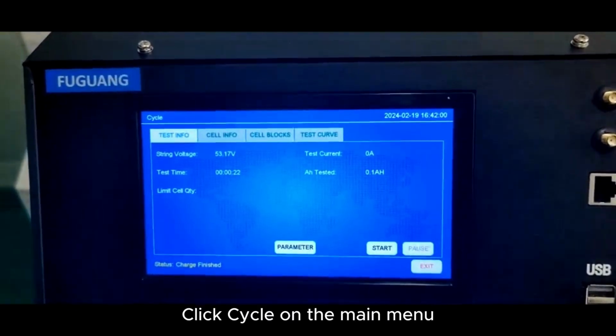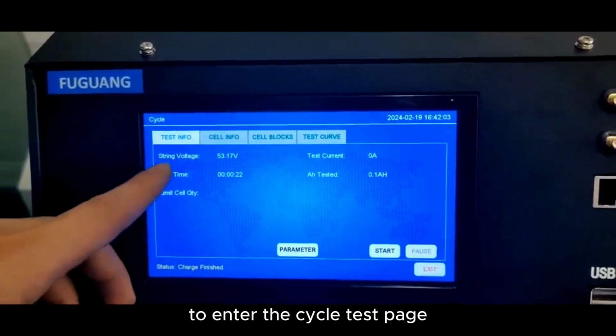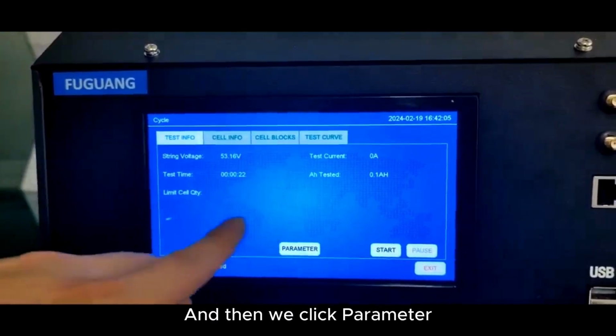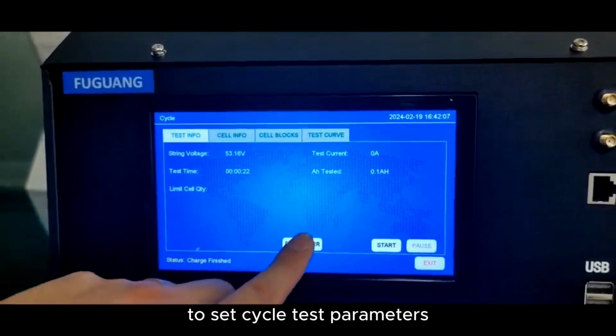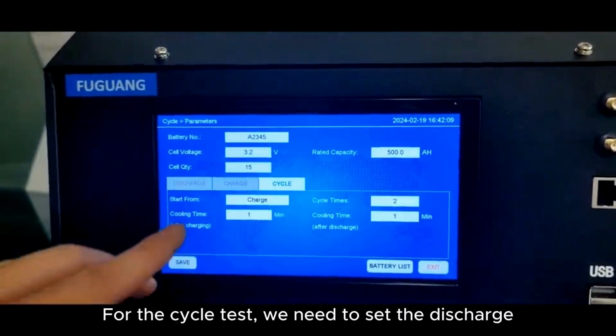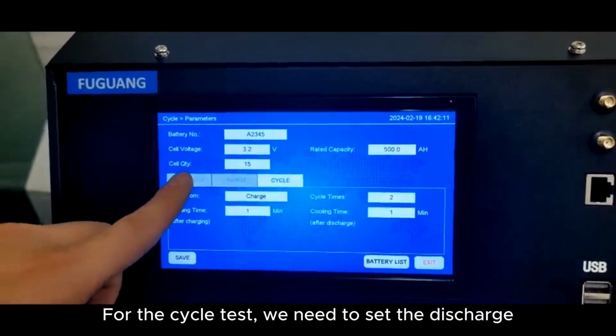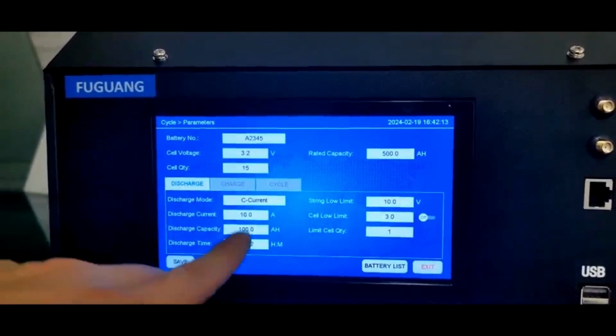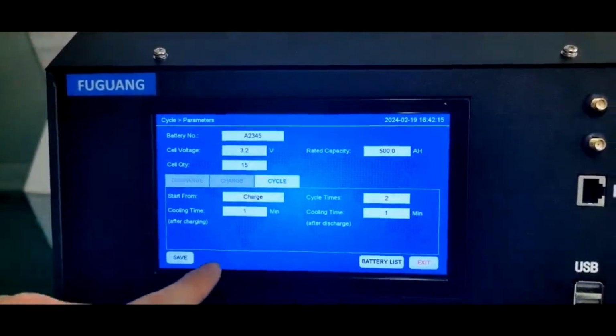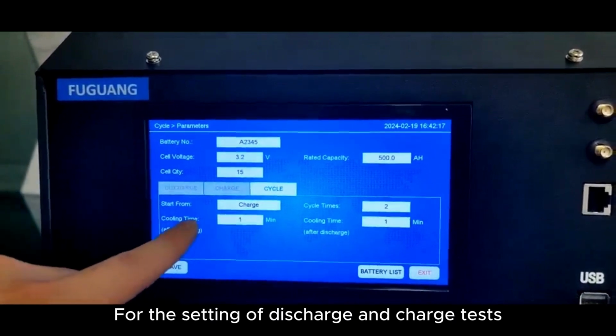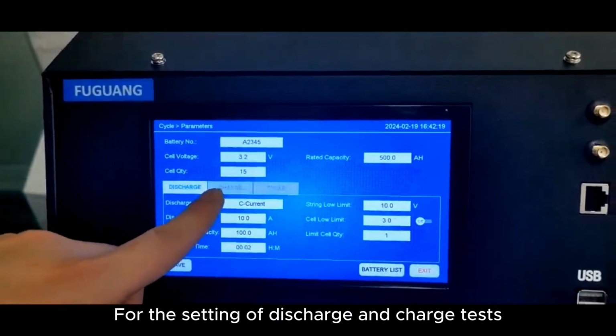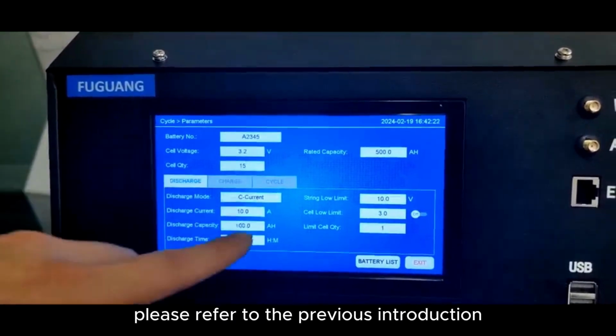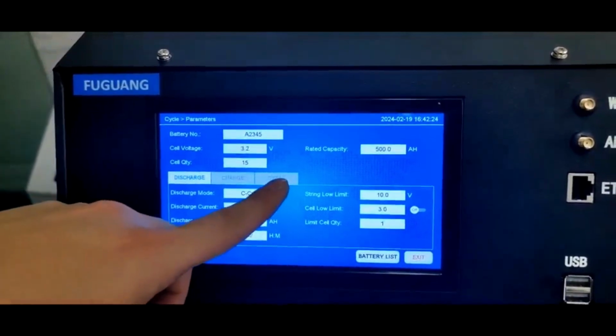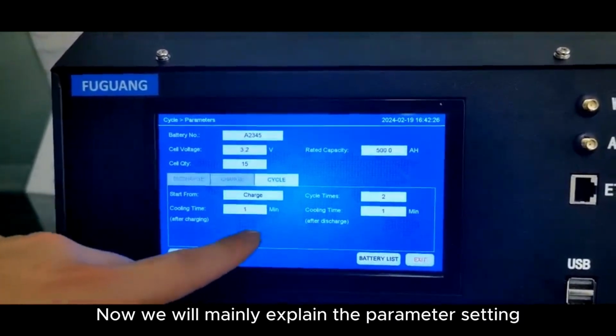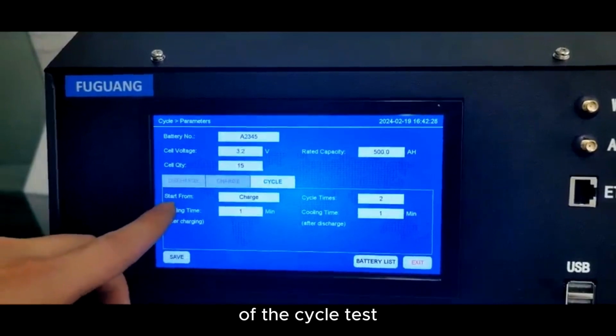Click Cycle on the main menu to enter the cycle test page. And then we click Parameter to set cycle test parameters. For the cycle test, we need to set the discharge, charge, and cycle parameters. For the setting of discharge and charge tests, please refer to the previous introduction. Now we will mainly explain the parameter setting of the cycle test.